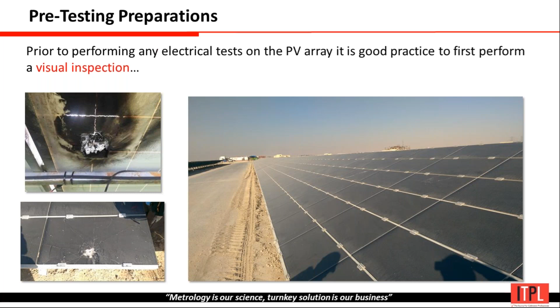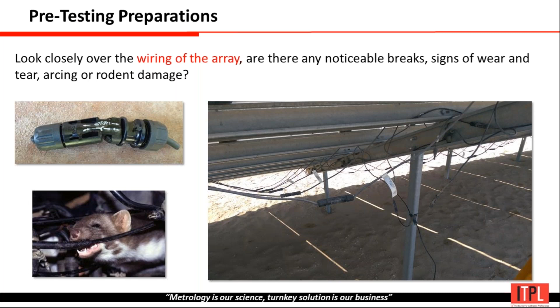It is a kind of visual inspection, we can say. From the visual inspection, we can directly decide whether we have to start the test, or whether we first have to see the condition of a panel or a string or the power plant. Then we start the testing. These are conditions we might face during the testing, like MC4 or MC3 connectors getting burnt, and some cable getting damaged. So every time we have to make sure of this before going for the testing and commissioning.